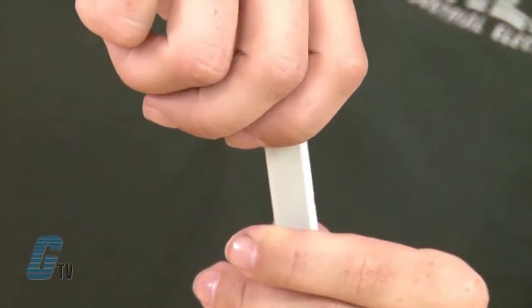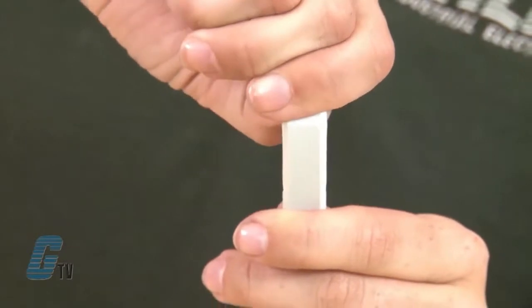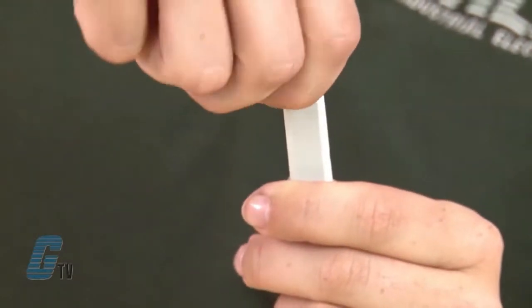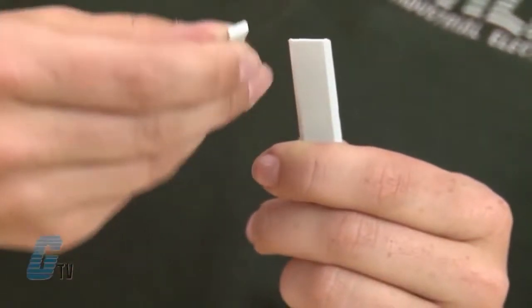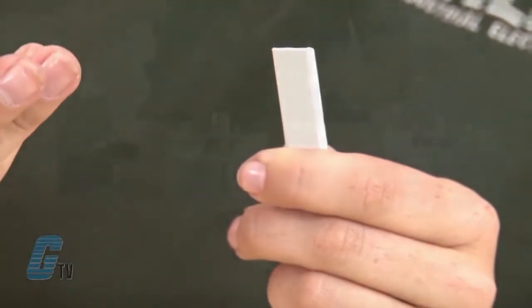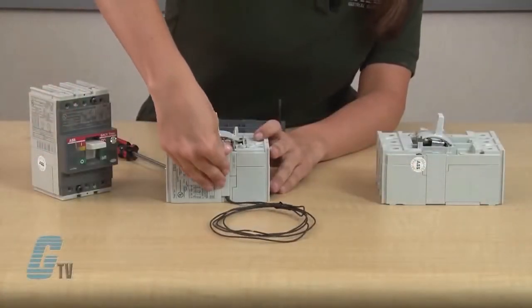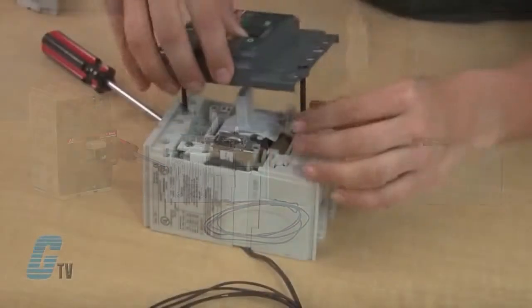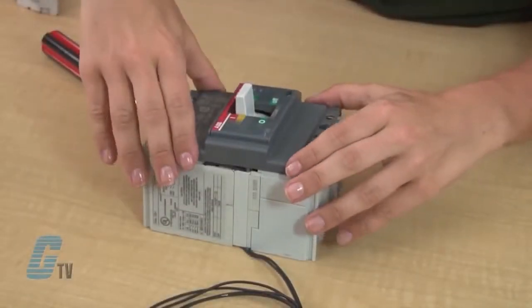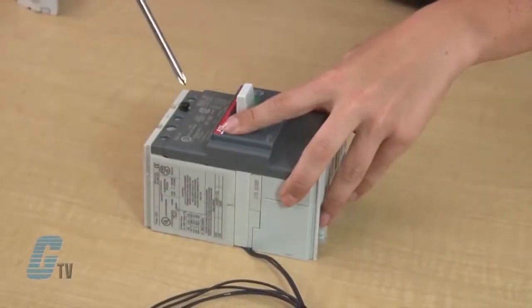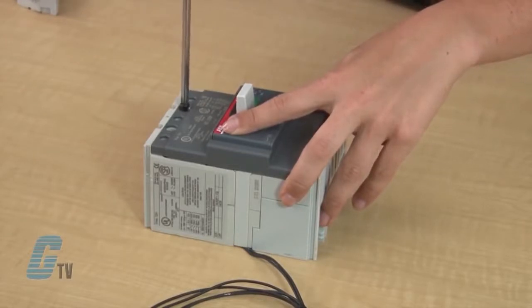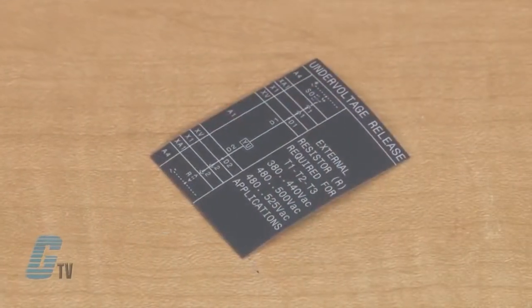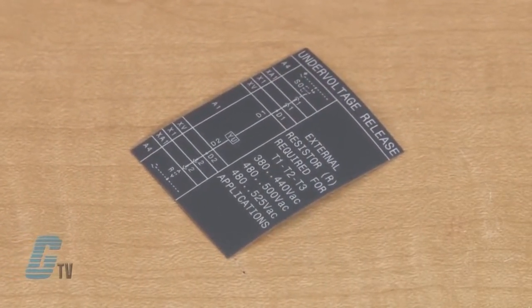To shorten the cover, I'll bend it back and forth here where it has been pre-scored and notched by the manufacturer until the part separates. Then the wire channel cover can be slid back into place. Now I will reinstall the front cover and fasten the screws to the frame. Finally, I will apply the legend decals on the side of the breaker for future reference.